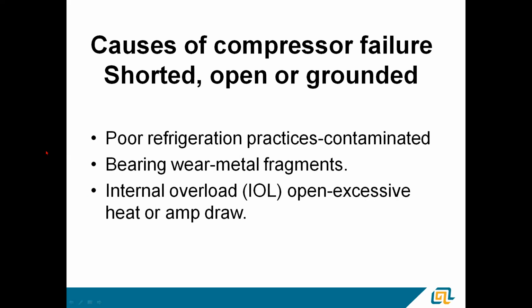Shorted, open, or grounded. Refrigeration practices are the first thing to come to mind. A contaminated system wasn't evacuated well enough. You replaced an R22 system, you put in an R410A system, but the R22 or the previous system had a compressor failure. You had contamination in the line sets, didn't clean out. So remember that, we're HVAC guys, but we're also refrigeration technicians. So keep that in mind. Cleanliness is the most important thing you can practice.